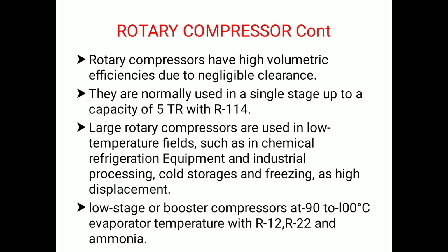Large rotary compressors are used in low temperature fields, such as in chemical refrigeration equipment and industrial processing, cold storage, and freezing as high displacement. Low stage or booster compressor at temperature limits of minus 90 to 100 degree Celsius evaporator temperature with R12, R22, and ammonia. So these are some important points regarding the rotary one.